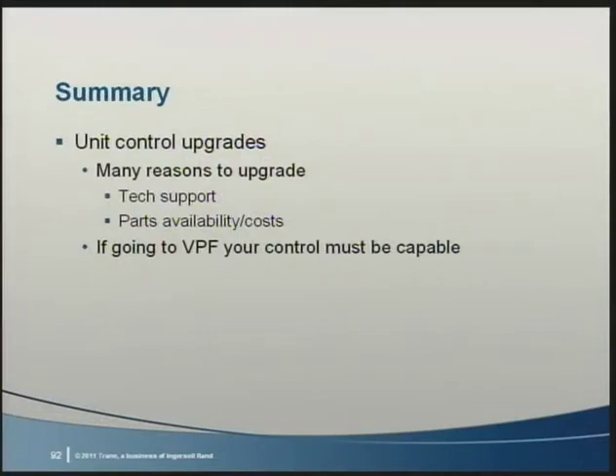Without upgraded controls with flow compensation, you may not save very much energy with the VSD in a variable flow setting. Consult with the chiller manufacturer to find out how suitable your existing chiller and chiller controls are for variable flow. Susanna, what about system level controls upgrades?